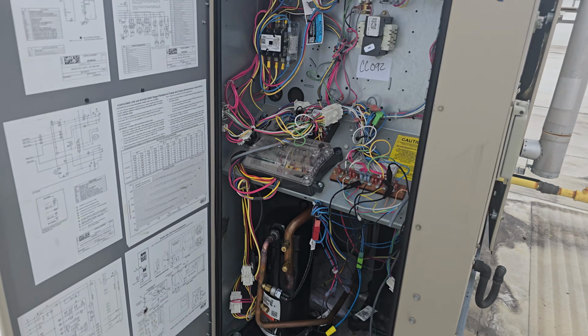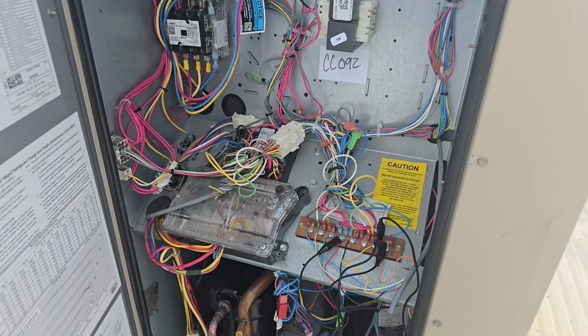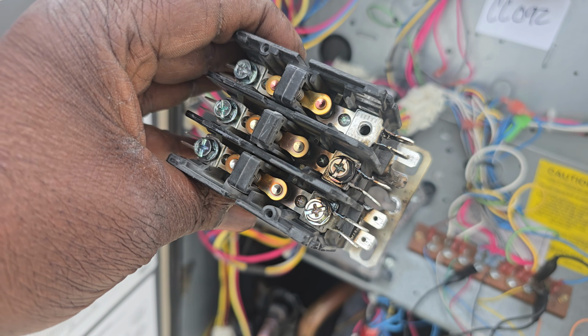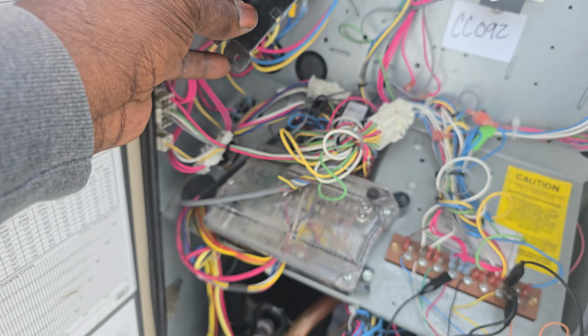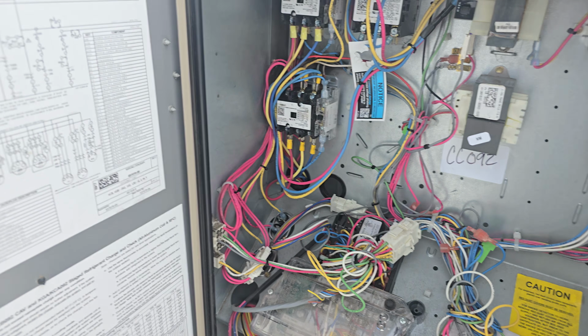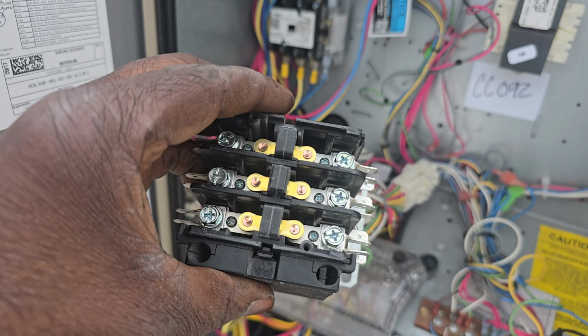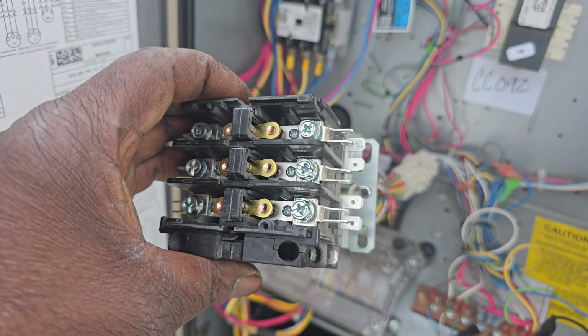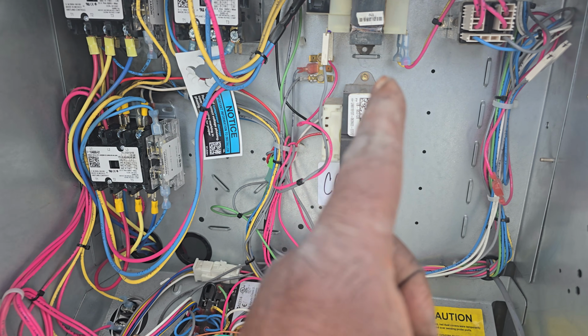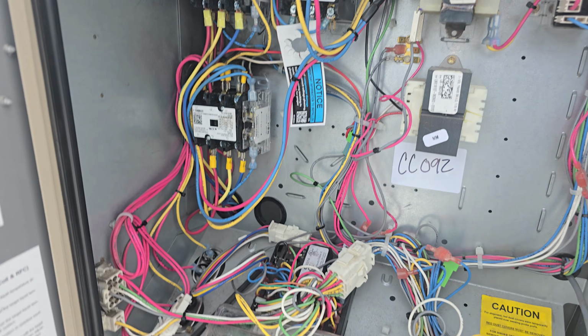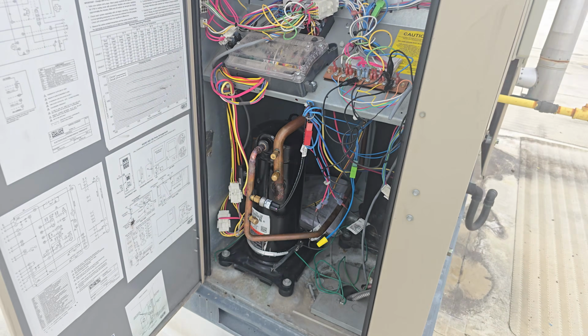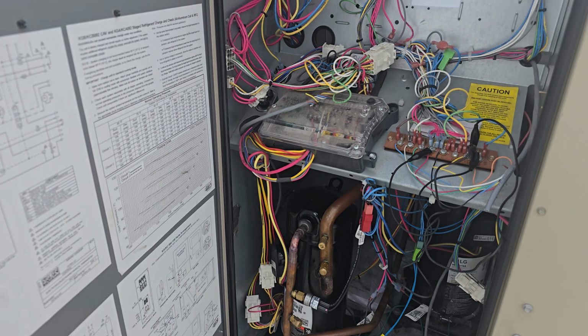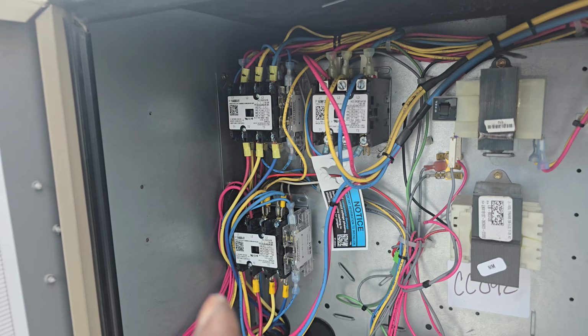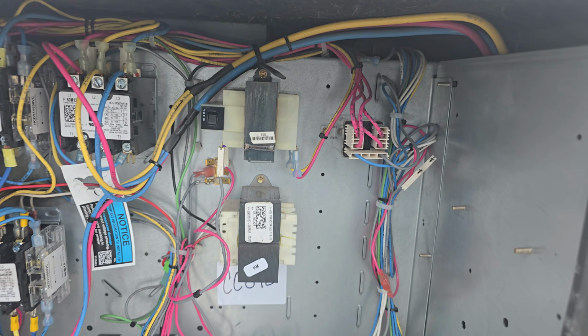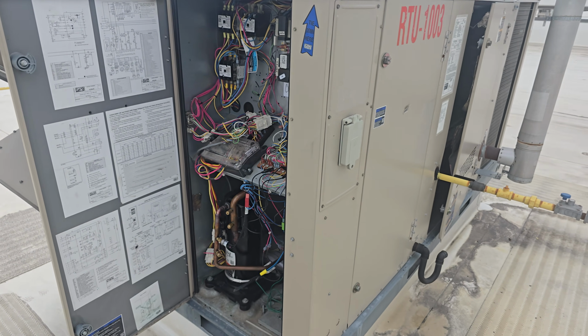So please, I'm going to just show you how bad the contactor is. Really bad. This was contactor number 2, but contactor number 1 wasn't really that bad, but that was where the unit was tripping off. But it was tripping off on the low voltage of the transformer. So that tells me that the problem wasn't from the high voltage. So therefore it is a low voltage issue. The low voltage issue is all surrounding the contactors and then the relay. So all of that is done now, and everything is okay.